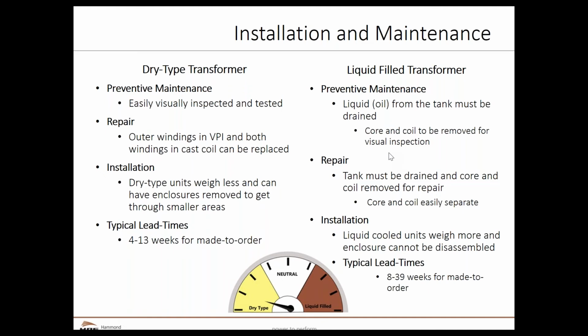Installation, liquid cooled transformers often weigh more. The enclosures can't be disassembled. You might be able to move it in without the oil, but then you'd have to bring in oil later on to fill it up. And typical lead times, as we've discussed, we've seen some lead times now of over a year, in some cases approaching 2 years for liquid filled transformers. And when we talk about those lead times, really we're talking about what we call medium voltage transformers. I believe high voltage transformers, lead times could be even longer than that.